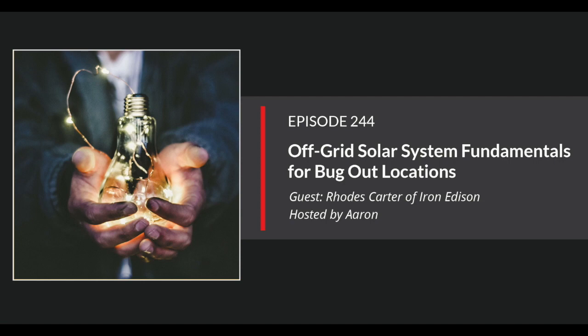So, to do a proper load calculation, we here at Iron Edison have a load calculation worksheet that we share with all of our prospective customers. It's really just an Excel spreadsheet where you go around the house counting light bulbs, literally, and other appliances. Put in the quantity of each item you have and how many hours a day you anticipate them being on, both in the winter months and in the summer months, because your electrical loads are going to vary from season to season. This worksheet will then calculate for us automatically how much energy in kilowatt hours you're going to use every day. And with that number, we can start designing a system that'll suit your needs.